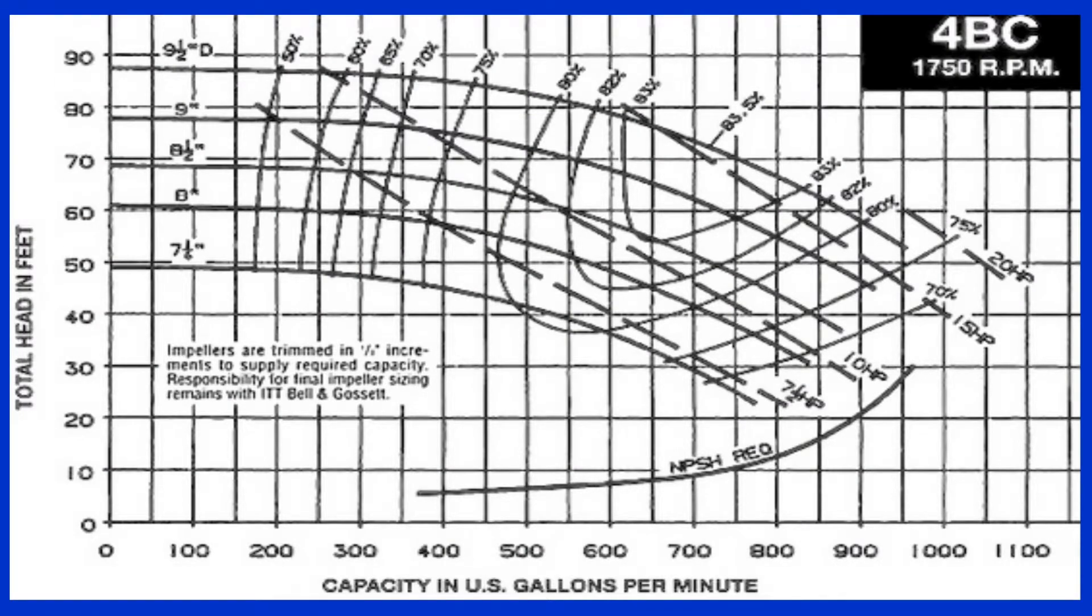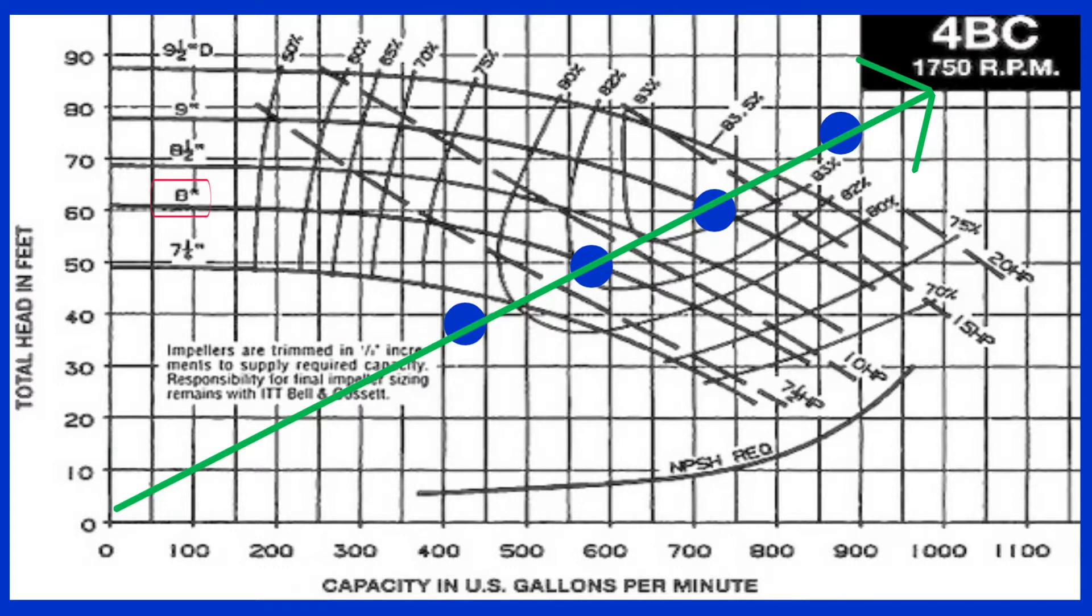We can now plot the TDH on the graph for our given flow rates, and see which is closest to intersecting the pump curve for our given pipe. It looks like the TDH for the flow rate of 575 gallons per minute is almost dead on to hit our pump curve for an 8-inch diameter impeller.